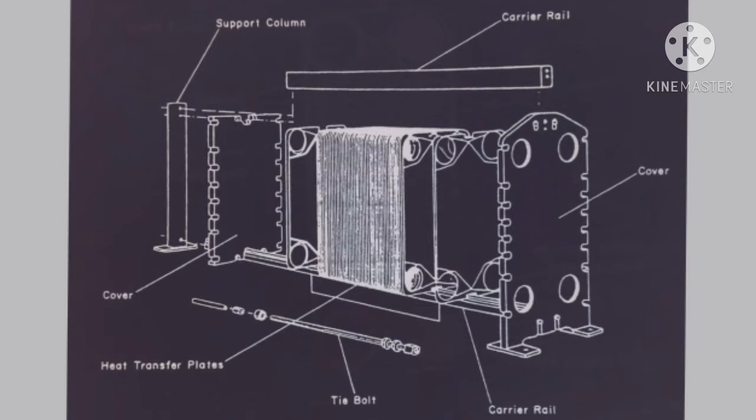That covers the advantages of plate type heat exchangers. Now the disadvantages. First disadvantage is initial cost is high, because plate type heat exchangers are made up of titanium plates, and titanium plates are expensive. Second disadvantage is finding leakage is difficult, since pressure testing is not as easy as with shell and tube type heat exchangers.